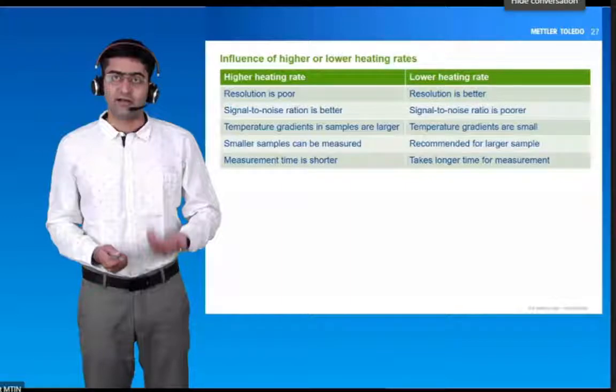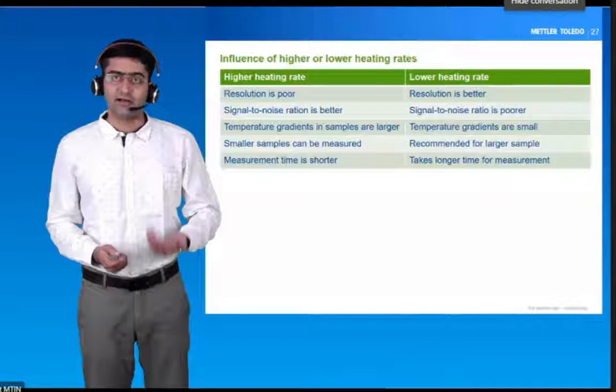You can see some of the effects of the heating rate on the results. For example, this is a decomposition of benzoyl peroxide. With different heating rates, you can see the sharpness and the signal-to-noise ratio. In a similar way, you can also see the melting sharpness as a function of heating rate.